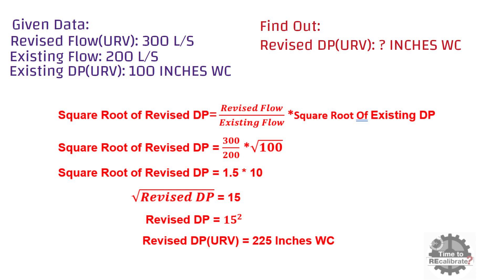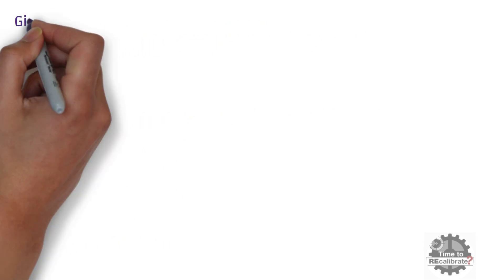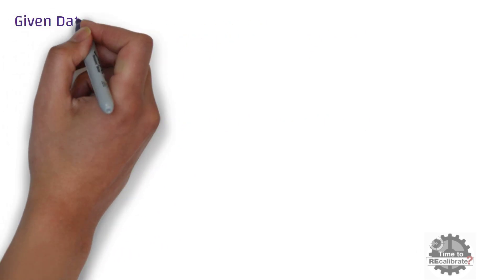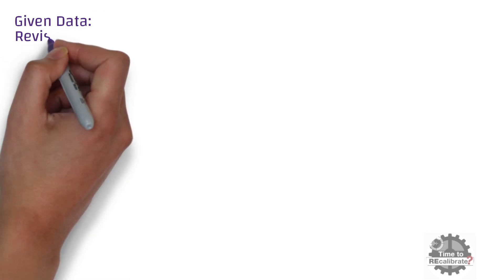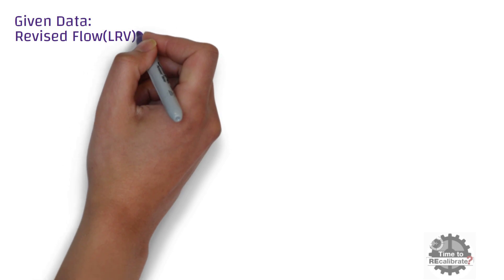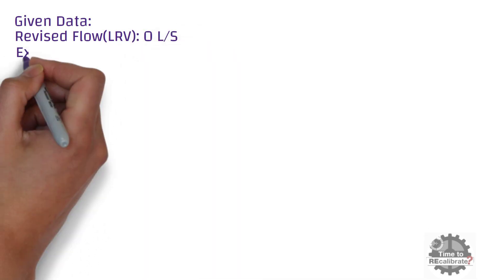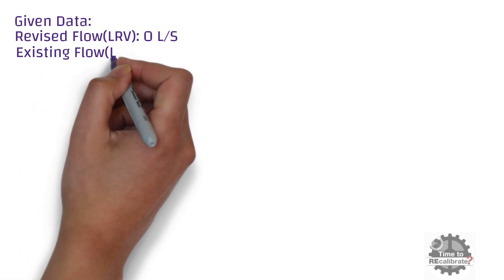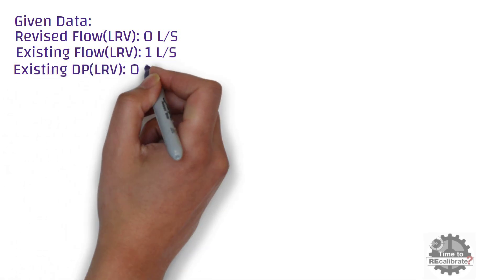Remember, this is only the upper range value of differential pressure; we still need to calculate the lower range of differential pressure. Let's write down the data for the lower differential pressure range. The revised flow lower range value is 0 liters per second, and the existing flow lower range value is 1 liter per second.